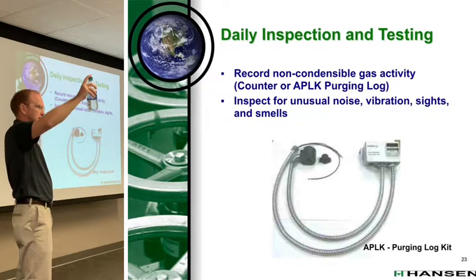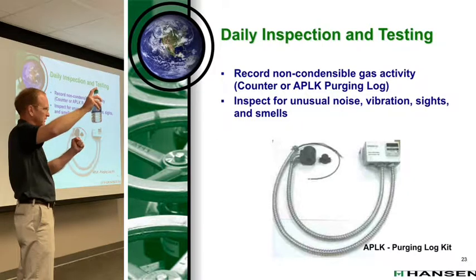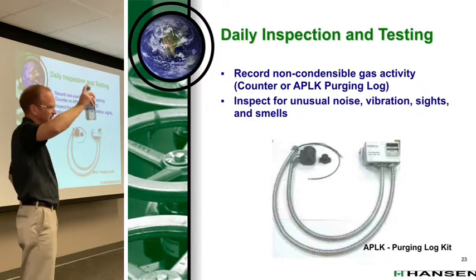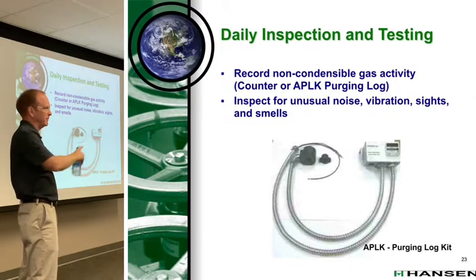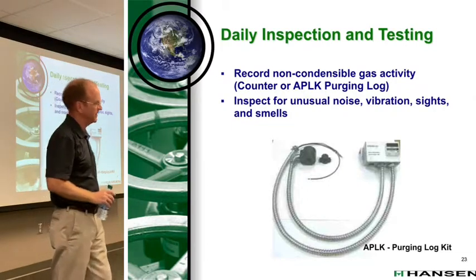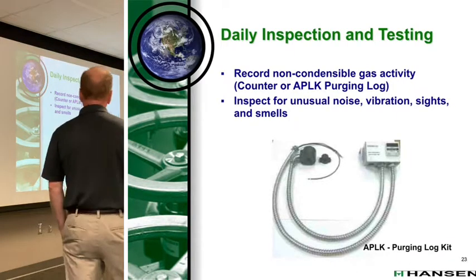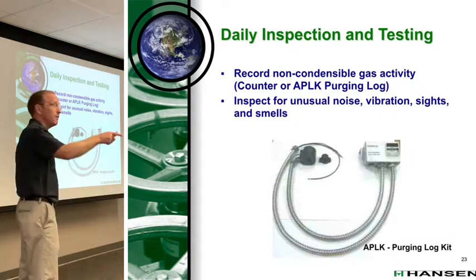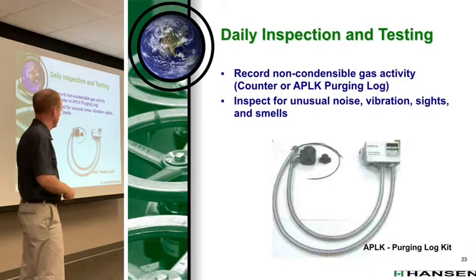But if you see that same activity with very, very small bubbles and cloudy looking, then you probably have a high concentration of ammonia in there. That's when you want to see what's going on. And if you do walk by it, you'll really notice the difference. That's when it's about to jump off the wall. Yeah, shut it down.